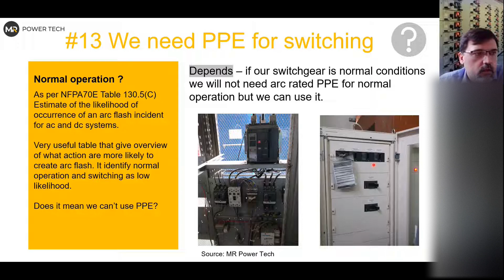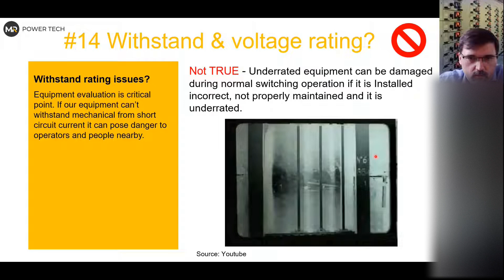Withstand and voltage rating. So we have to catch up a bit because we are running out of time. Withstanding issues. If you never check your installation, you don't need to check the equipment evaluation if the equipment is properly rated, it was designed well, and so on, that's fine. If you have a document that says that against a short circuit current of 50 kiloamps you have equipment rated 65, that's fine. But if you have a 65 kiloamp short circuit current and your equipment is rated 50 kiloamps, that's not okay, because it might lead to an accident just during normal operation.